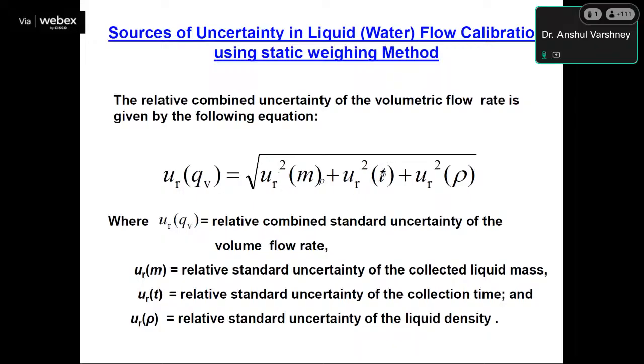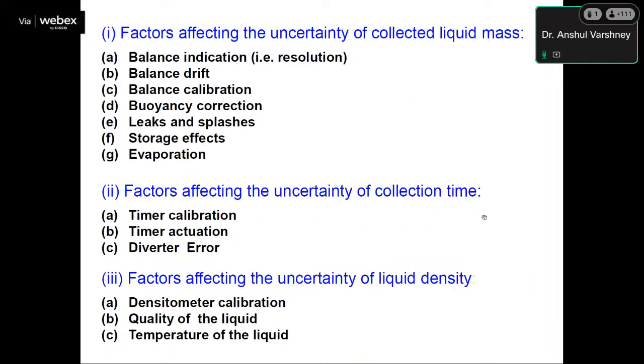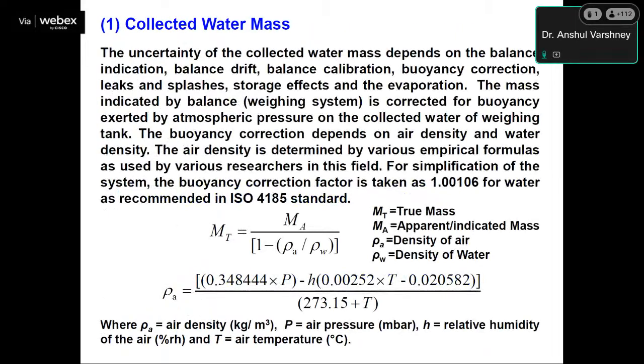This is the uncertainty for collection time, and this is for density. So the factors affecting the uncertainty of collected liquid mass are balance indication, balance drift, balance calibration, buoyancy correction, leaks and splashes, storage effect, and evaporation. Similarly, for collection time, there are timer calibration, timer actuation, and diverter error, and for liquid density, densitometer calibration, quality of the liquid, and temperature of the liquid. These are some factors affecting the uncertainty of the overall system.